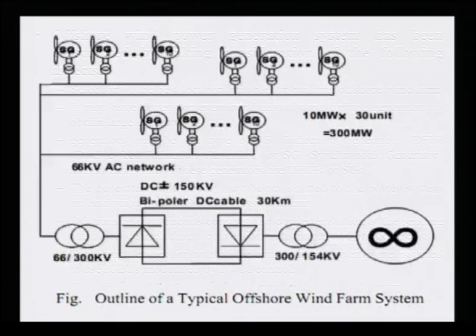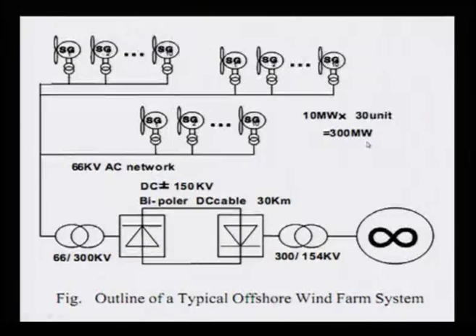Also, without HVDC Light there will be a problem of commutation failure on these two sides of the HVDC line we are talking about. That can also be recovered by using HVDC Light. With HVDC Light, converter 1 still has the commutation failure, but the DC voltage only decreases to a certain level, 300 kilovolt, while it operates at plus or minus 500 kilovolt. HVDC 2 does not have any commutation failure, and its DC voltage only decreases to 0.8.